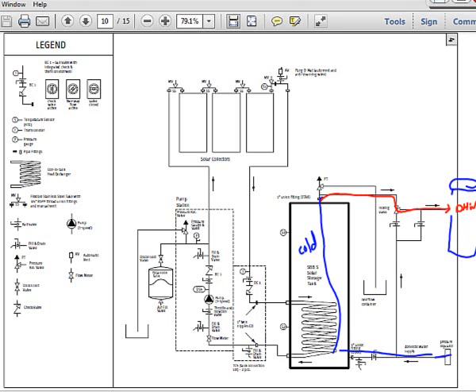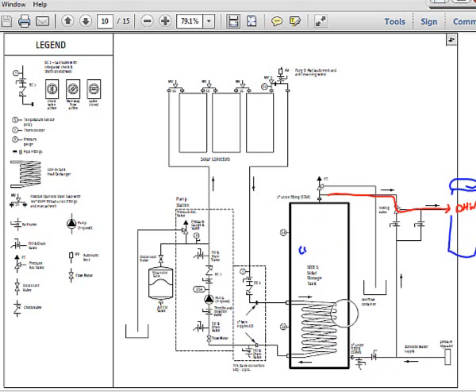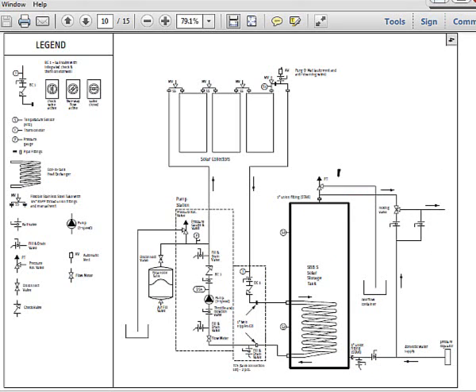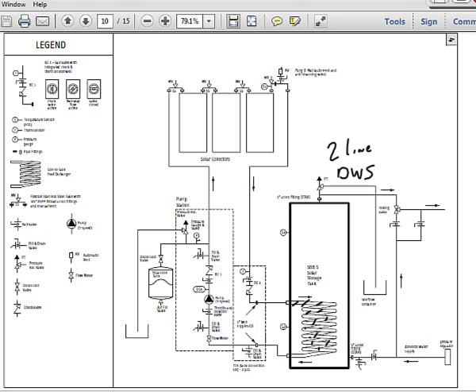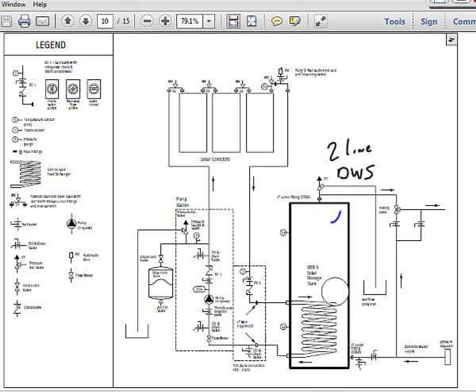There's two mechanisms. I could avoid the domestic hot water tank on the right-hand side and just keep with this thing. In this particular case, I could not. I would have to have a secondary coil internal to it to continually provide heat into this storage tank. But one problem that we need to worry about is the domestic water supply, the DWS, that is flowing here, needs a double line, two linings of protection from the glycol mix. And unfortunately, this system only has one coil here. This may not be a satisfactory means of thermal transfer. You have to check with your municipality to verify that that is an acceptable practice, to have the tank itself store the liquid for the domestic water supply and out.